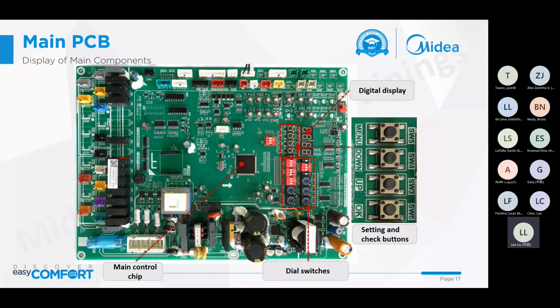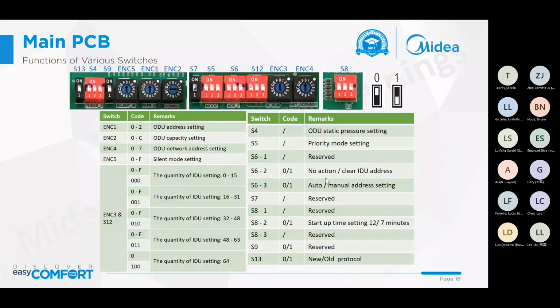We can check voltage, temperature, pressure, and under the menu switch, there's a DIP switch. Yes, DIP switch for some basic settings. And for function of the DIP switch, we can see the different types of the DIP switch. This switch is used to set the outdoor unit address and outdoor unit capacity, outdoor unit network address, and we can also set some silent mode.